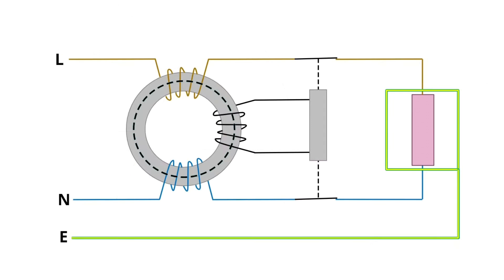This has the effect of slightly magnetising the magnetic core in one direction, leaving a slight magnetic field in there all the time. Now, if an earth fault occurs, the magnetic field around the neutral is slightly weaker, but because there is a weak permanent magnetic field inside the soft iron core, there isn't enough strength in the imbalanced field to overcome that slight remaining magnetism and generate enough current in the tripping coil to disconnect the circuit. So, the device simply won't trip.